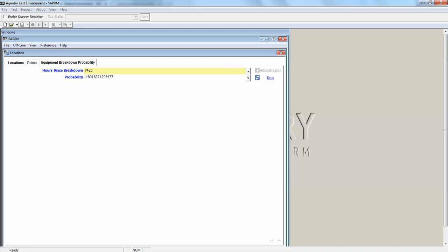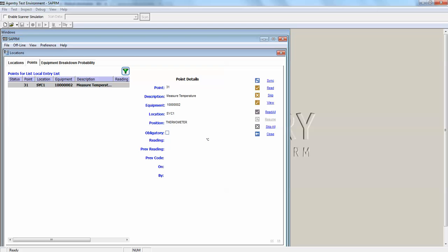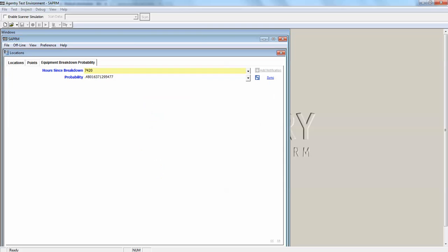The second stage of predictive maintenance is obviously based on the different values collected on the machine. It also could include environmental variables or process variables, and creating a regression out of it to understand which are the main contributors of the breakdown, and then based on those readings that we take, based on those points that we collect now, we also show what is the probability of the breakdown. So that is stage two, which is more effort consuming, but this is the start point for predictive maintenance.